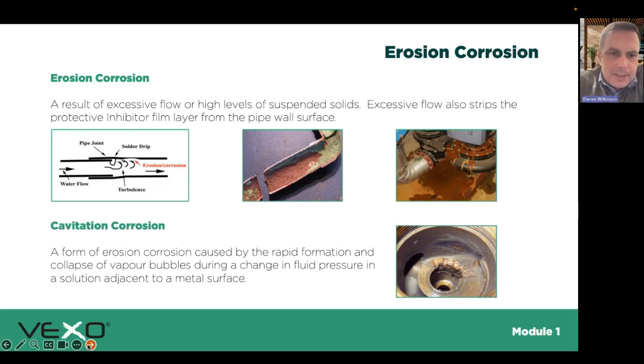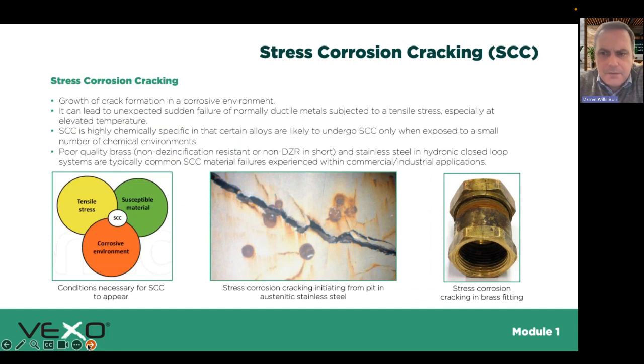And then cavitation is another form of corrosion. So rapid formation or collapse of vapor bubbles at a change in fluid pressure adjacent to the actual metal surface. So we can see this, typically, in pump impellers, for example, if maybe they're not quite balanced correctly, or the flow rate or the demand into the pump isn't being met. You can hear cavitation as well, pumps in particular, this kind of rattling, like they've got a bag of nails rattling around inside, and that can be extremely damaging. So that is another form.